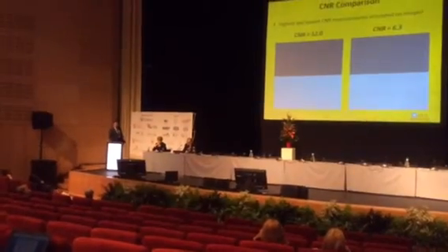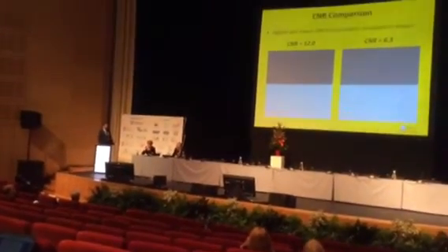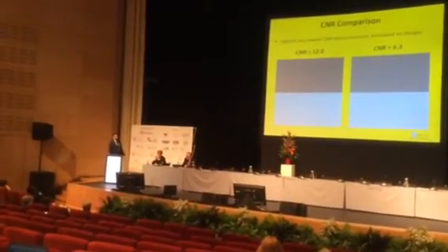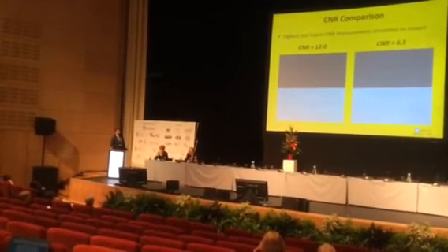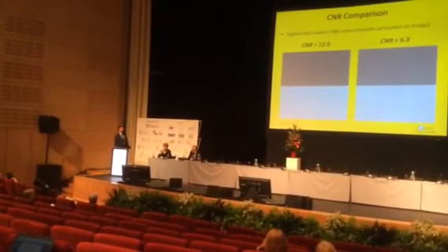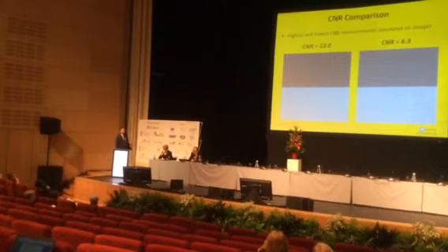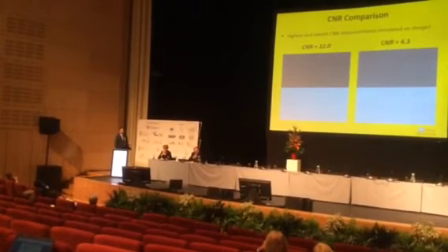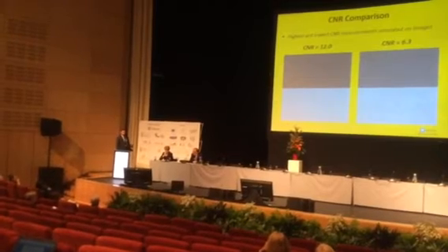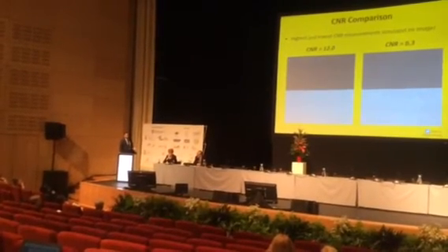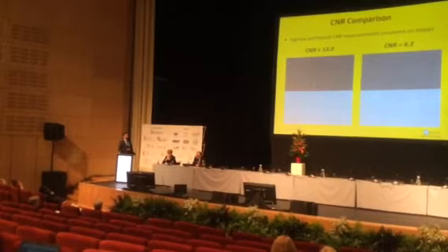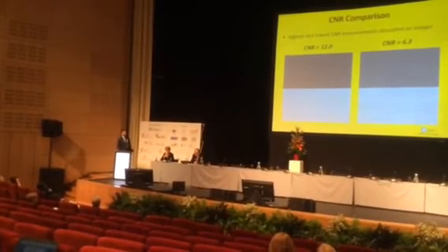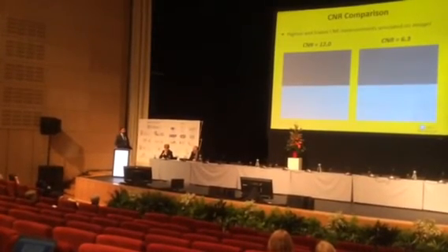So in order to try and give you an idea of what the difference in the contrast to noise ratios actually do in terms of the image quality, I've taken the highest value that we got, which was 12, and the lowest value that I got was 6.3. And using identical pixel value and noise data that I obtained from the phantom images, I've simulated the two images in ImageJ, and displayed them at the same window level in order to try and demonstrate how the contrast to noise ratio does affect the image quality. And hopefully you can clearly see that the image on the left there has got better contrast and much less noise than the image on the right.